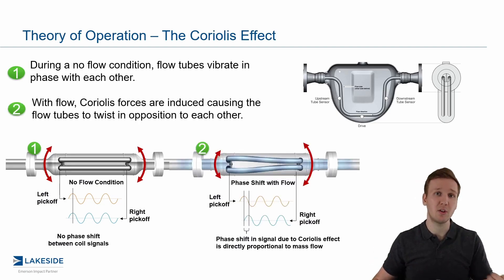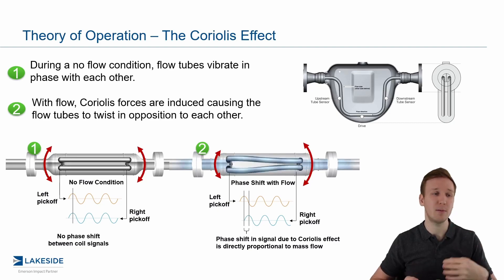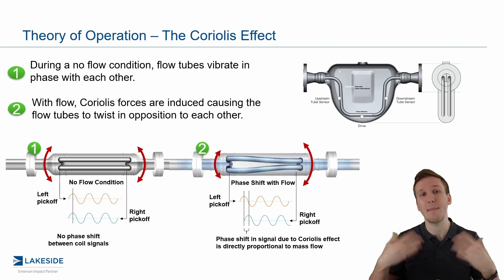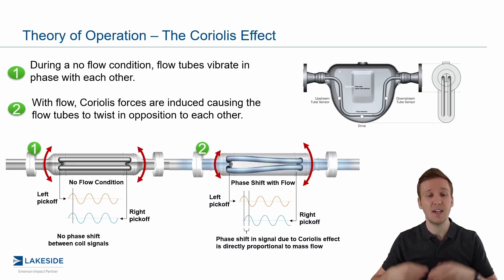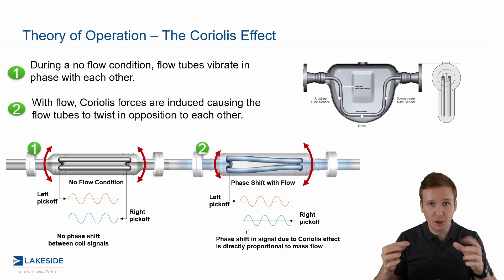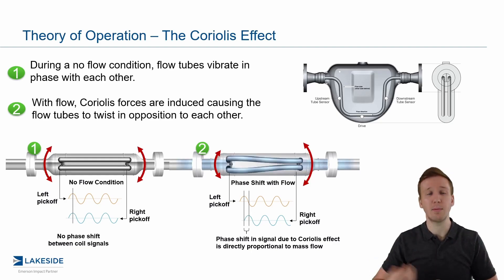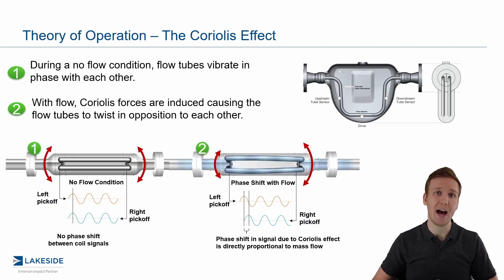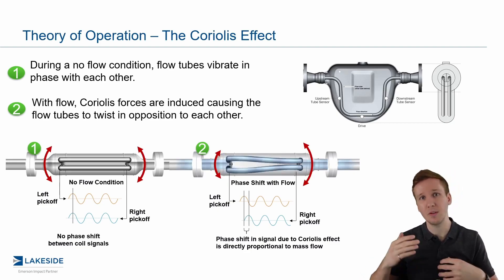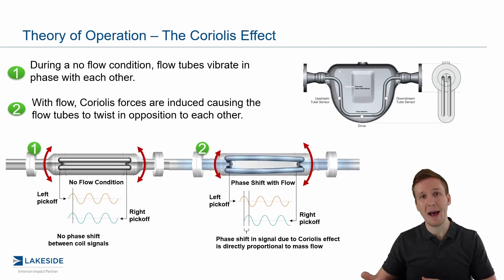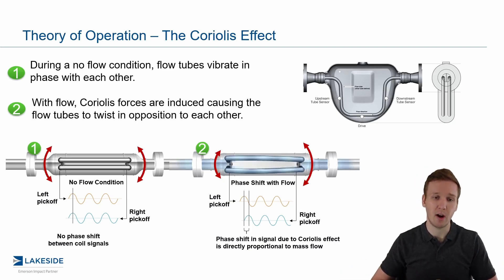When we introduce flow, we see the Coriolis effect — a deviation between the left side and the right side. They become out of sync with one another, and that phase shift difference is directly measured and is directly proportional to mass flow rate. We put it through our calibration lab, determine how many milliseconds equals a specific mass flow rate, and from that point on it is a linear equation.